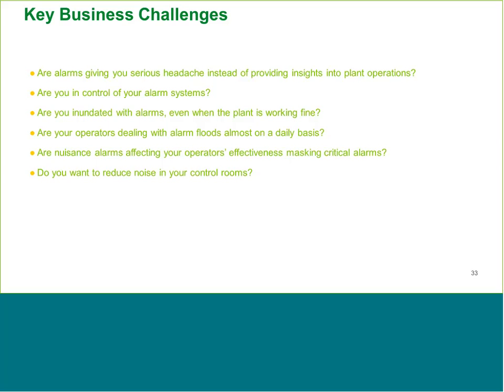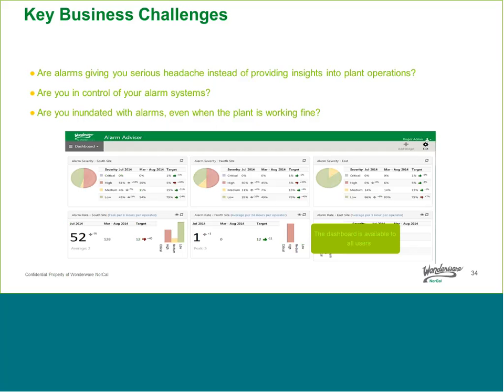So very common issues that we see in the alarming world at any given SCADA system or water wastewater plant, that we'll walk into a control room, we'll see a bunch of red alarms flashing on a screen, and the operator isn't really doing anything or reacting because that's just normal. It's normal to have lots of alarms, and they don't really pay attention to them. And really, that's a result of not building an effective alarm management system. And so if you're not paying attention to alarms, then you can miss the critical ones, and that's a problem, right? We're trying to run in regulatory compliance, avoid being fined, produce safe water, and run our plant reliably and efficiently. So we really need to manage our alarms effectively.